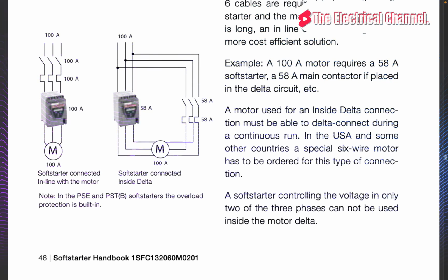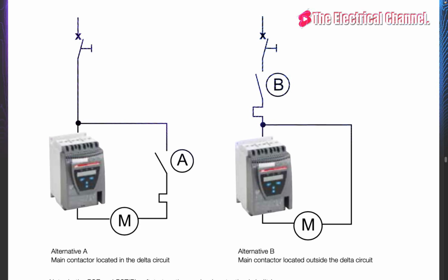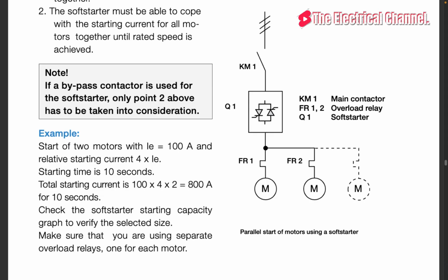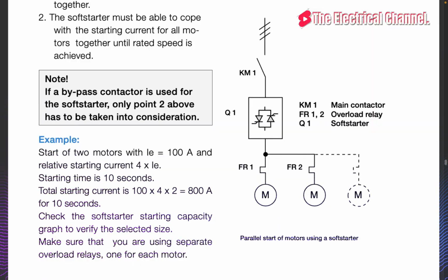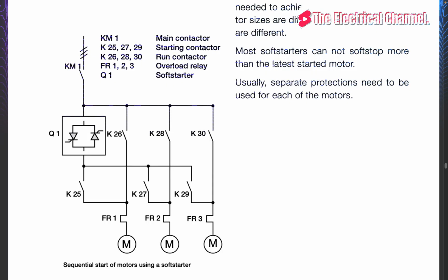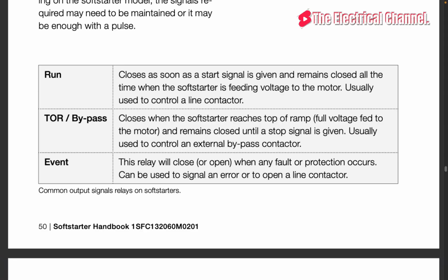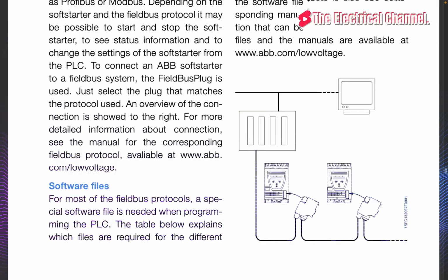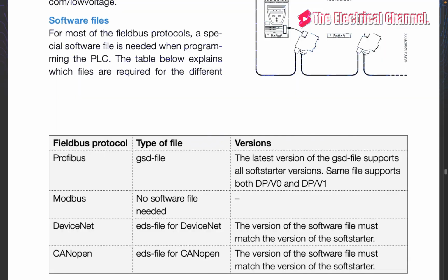Sometimes fluid couplings are used to reduce transfer torque. This method is expensive and requires a lot of maintenance. Since the star delta starter will reduce the torque in the start connection, it is not possible to use this starting method when the load torque is close to the rated motor torque during start. A star delta starter can only be used successfully with a very lightly loaded conveyor belt.